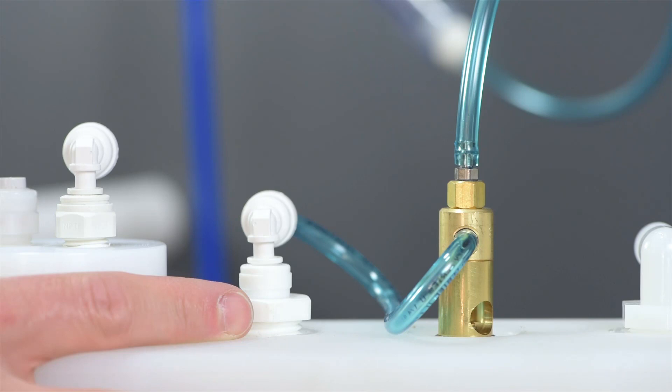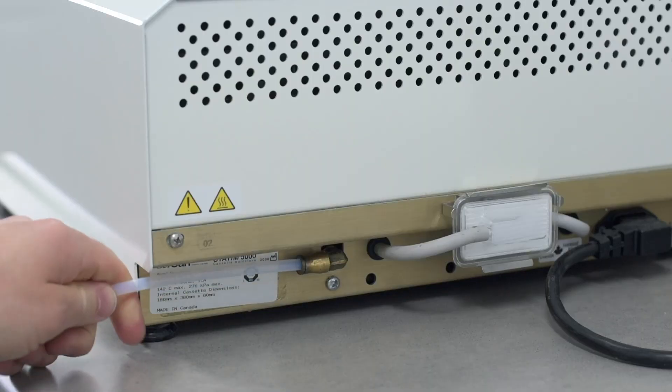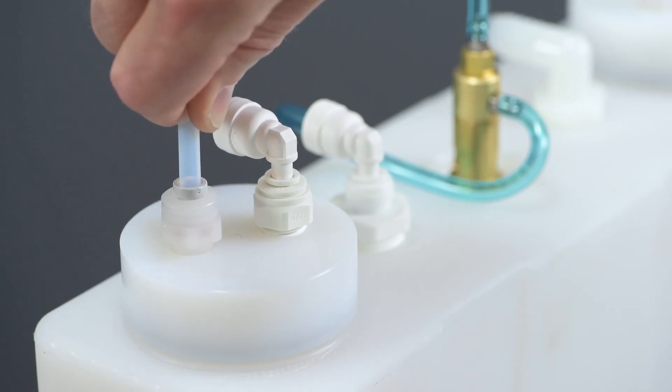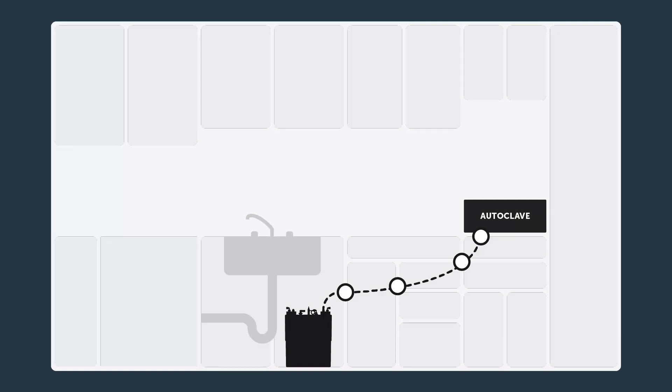Connect the 1/4 inch high temp Teflon tubing from the autoclave to the milky white Kynar fitting on top of the white manifold. Make sure the tubing doesn't kink when moving the autoclave or pulling the tubing through the cabinet partition holes.